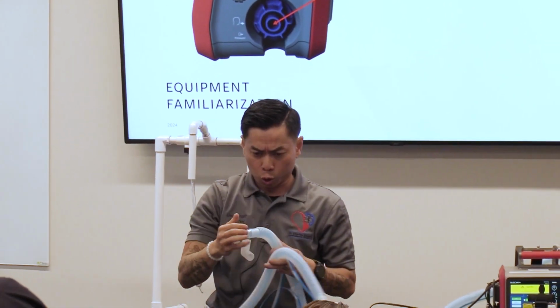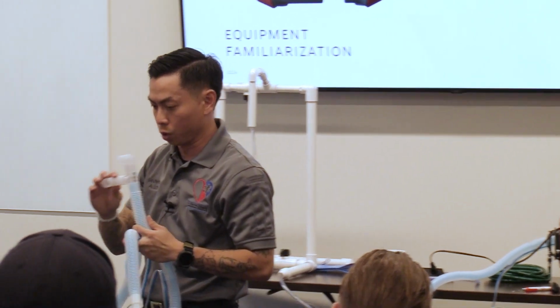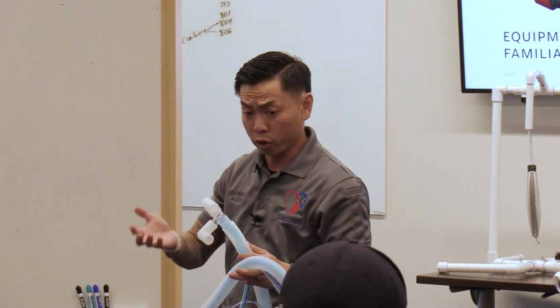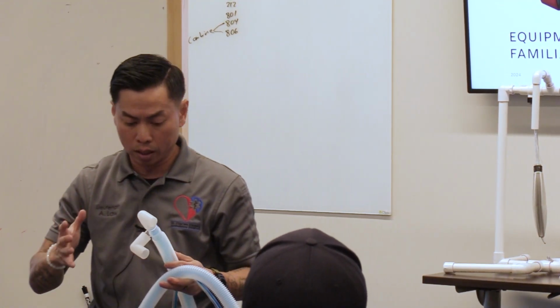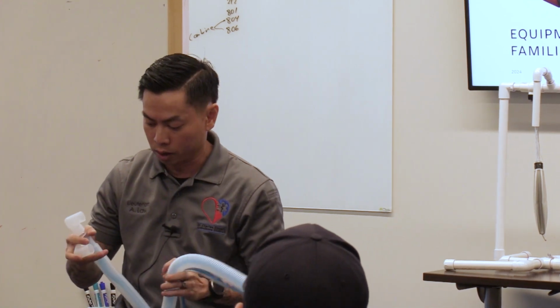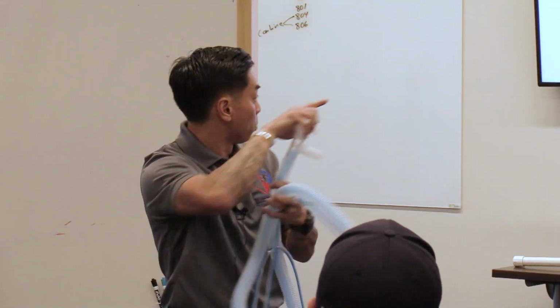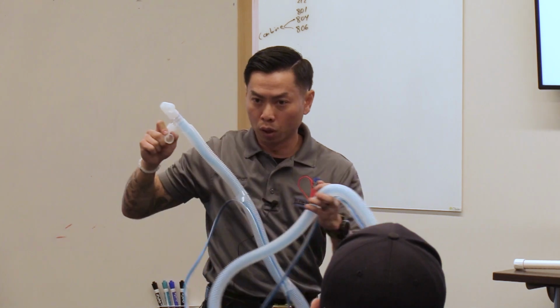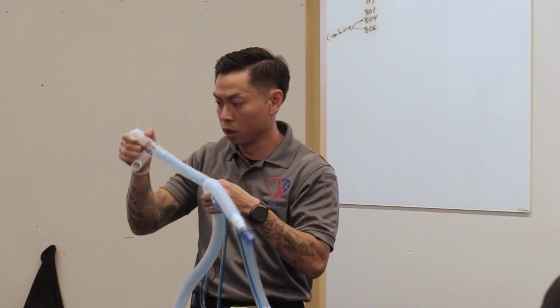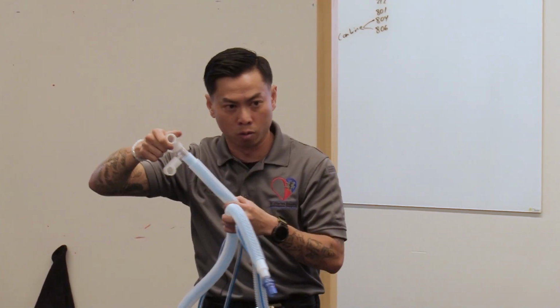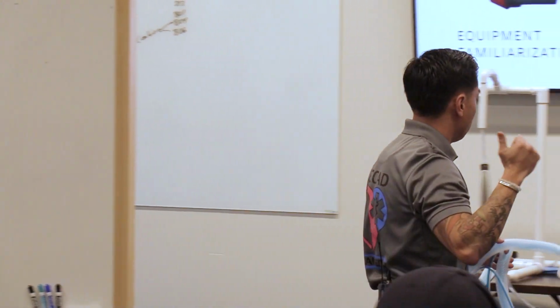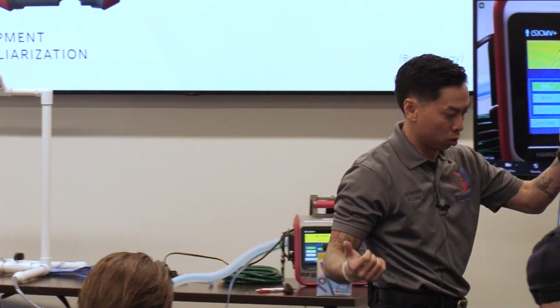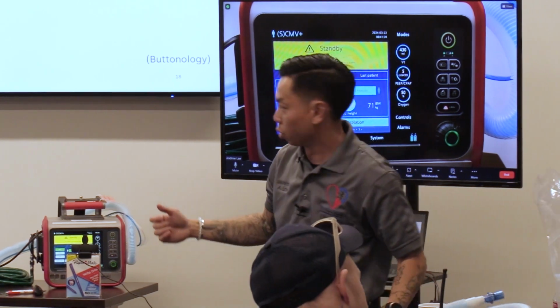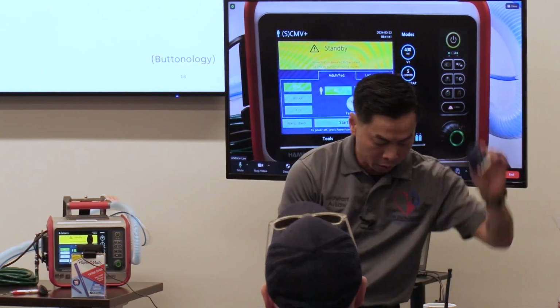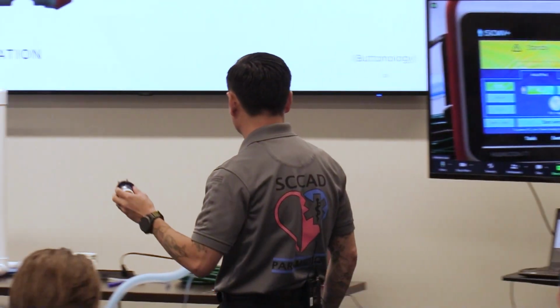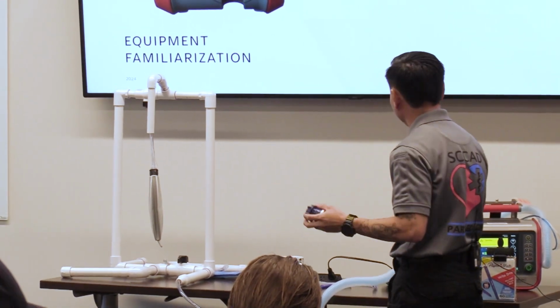Again, these are trained circuits that have been manipulated quite a bit, so they're pretty pliable. A fresh circuit is a pain to get on. One of the things I would suggest is to use the bottom one in that expiratory valve, plug that in first. Once that's in, you can manipulate that top piece and turn it around and get it in. Your ventilator's not set up to plug this in right now because we're still missing a piece. I know the image has this valve on there, but you guys don't have that piece plugged in yet, so that's why you can't attach your circuit yet, but we're getting there.